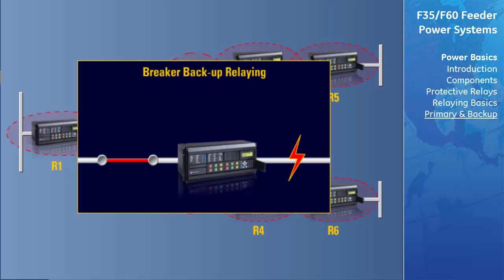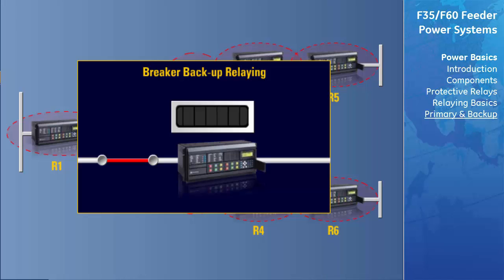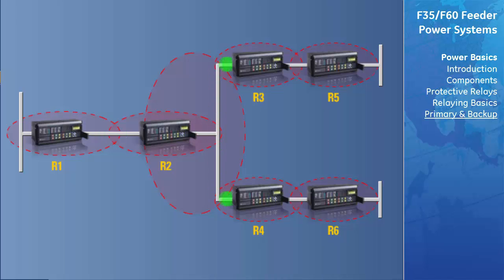Let's look at an example of a breaker failure protective element. In this example, the protective relays operate correctly, but the associated circuit breaker fails to clear the fault because of some malfunction within the breaker or its control circuits. The fault will remain on the system until some other means is used to clear it. The primary or backup relays start a timer once a fault has been detected, and the timer will time out and send a trip signal to all breakers that can feed the failed breaker with power.